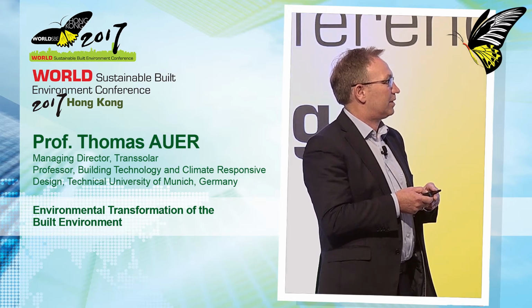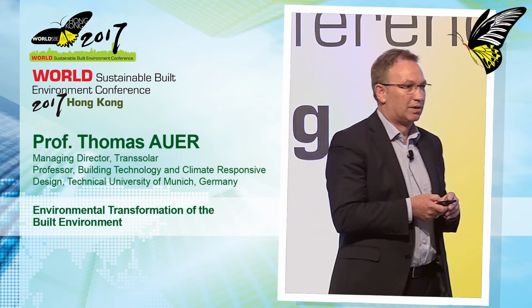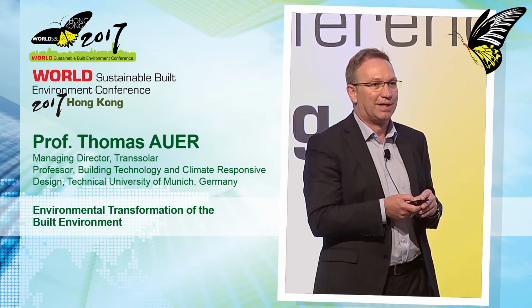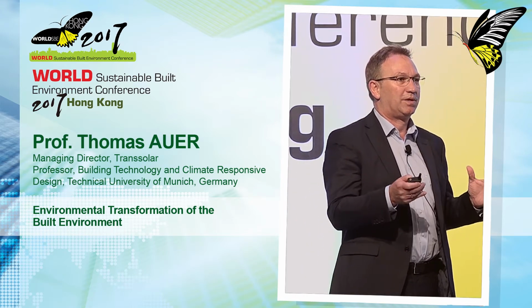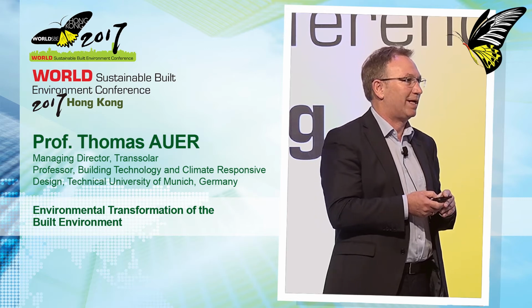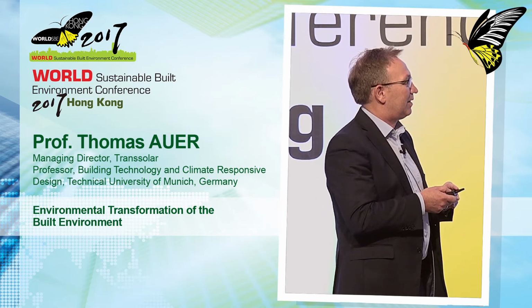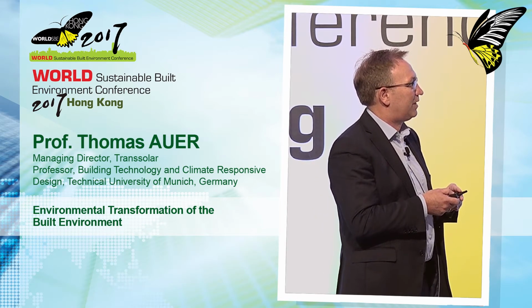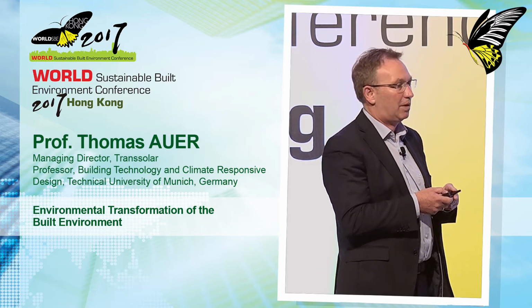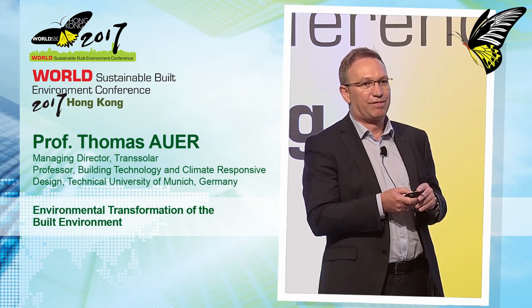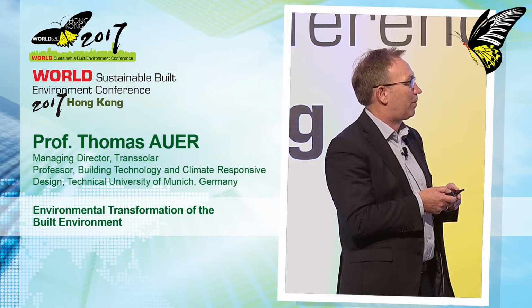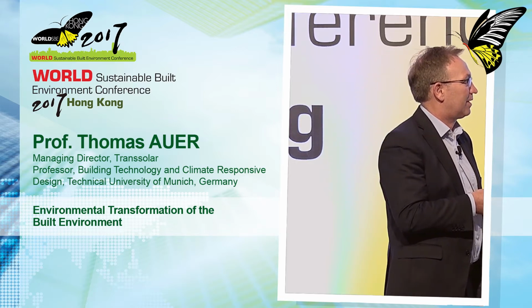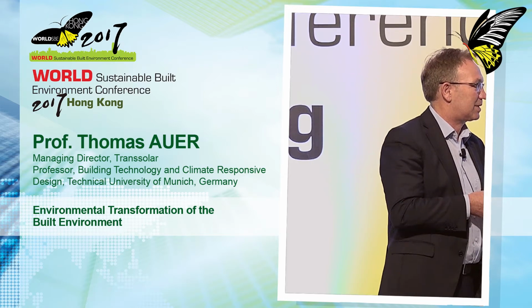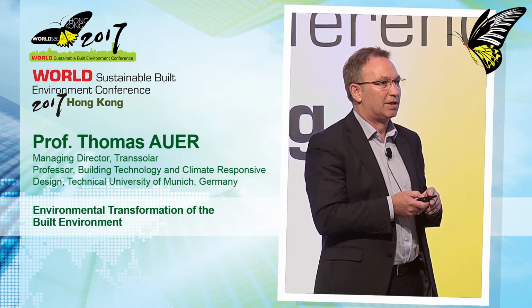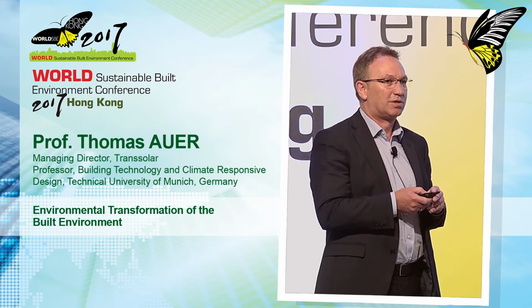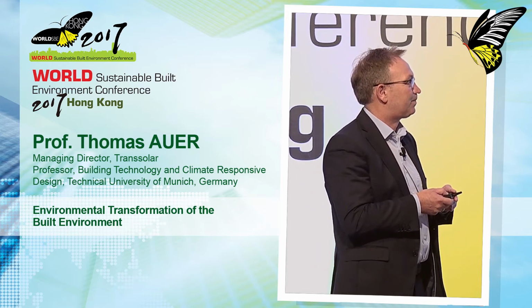In winter, we get the air into the winter garden. We condition the winter garden only to 10 degrees so the air can absorb solar energy. Then we take the air from the winter garden, humidified by a water feature, and distribute it through a raised floor plenum into the depth of the floor plate. We take it out at the north side of the building, down into the basement, where we have a heat recovery unit that takes heat from the exhaust air and puts it back into the supply air.